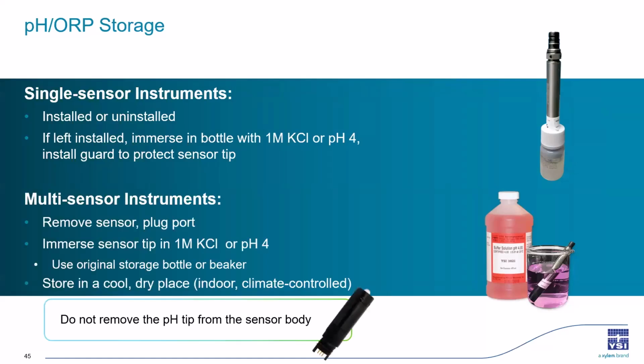If you have a multi-sensor instrument, you can remove the pH sensor and just make sure you plug the bulkhead port that you removed it from, and then immerse the sensor in storage solution. You can use the original storage bottle that it was shipped with if you had kept that, or just a beaker if you don't have that bottle anymore. Then store the sensor in a cool, dry place.